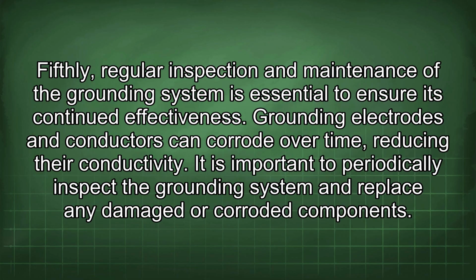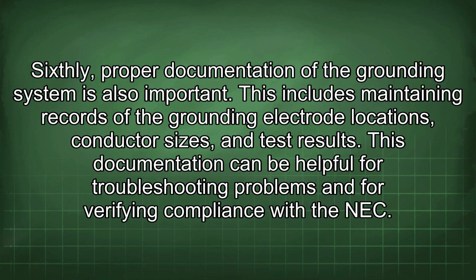Fifthly, regular inspection and maintenance of the grounding system is essential to ensure its continued effectiveness. Grounding electrodes and conductors can corrode over time, reducing their conductivity. It is important to periodically inspect the grounding system and replace any damaged or corroded components. Sixthly, proper documentation of the grounding system is also important. This includes maintaining records of the grounding electrode locations, conductor sizes, and test results. This documentation can be helpful for troubleshooting problems and for verifying compliance with the NEC.